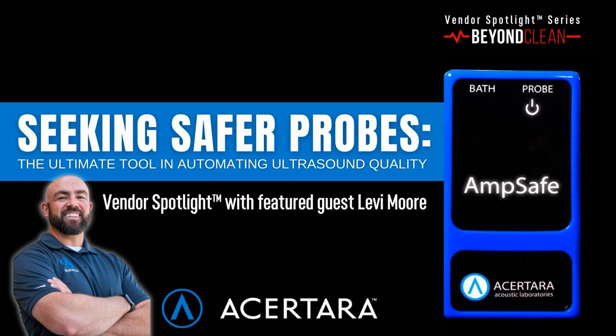This is one of those areas that I feel like has come into a little bit more focus for sterile processing than before. I feel like a lot of facilities are trying to centralize the reprocessing with the experts. And so TEE probes are one of those that have come in, as well as you see a lot more departments doing flexible scopes for GI that they didn't do before. And when I was still educating for another company I worked for, I actually did some education around leakage testing and was always trying to make that distinction between this is what you think of usually with leak testing, but there's this other one. And what I'm kind of used to is this blue bin and a couple of electrodes get dropped into the water and you're connecting them to the probe to test for leakage.